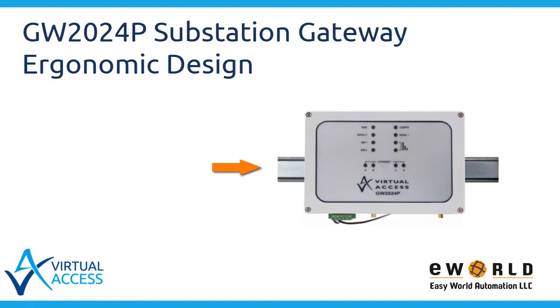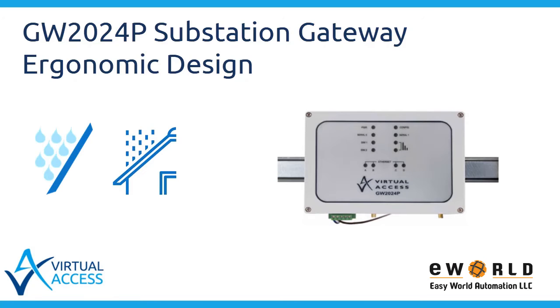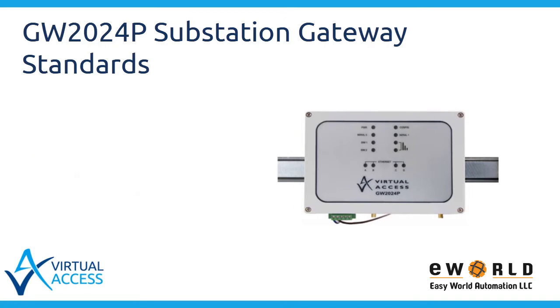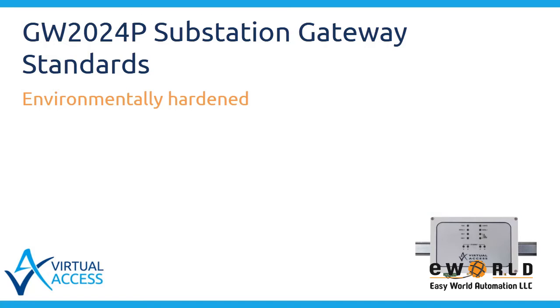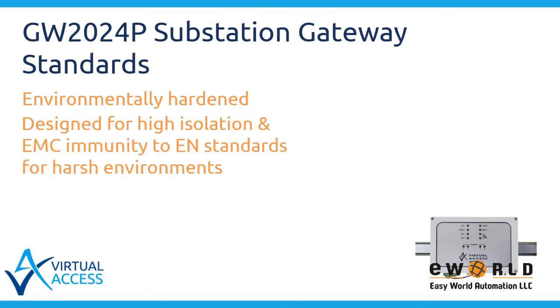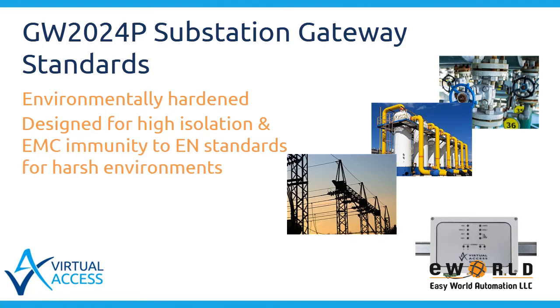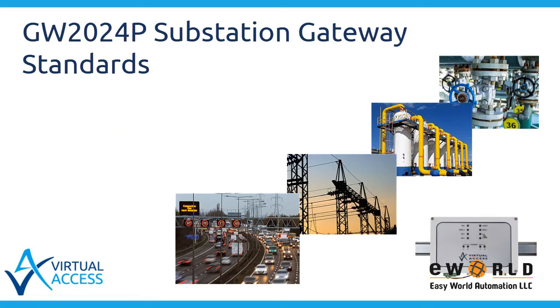second SIM slot. The GW2024P Substation Gateway can be mounted on a DIN rail with the connectors facing down for maximum environmental protection. LEDs face outwards for ease of reading by the maintenance staff and to protect against rain and dust. The unit is completely sealed other than the bottom connector. The GW2024P Substation Gateway is an environmentally hardened LTE router designed for high isolation and EMC immunity to EN standards for harsh environments such as water, gas, and electric power stations, rail, and roads. The device is designed to meet EMC, safety, ESD, and isolation standards mandated by these applications.